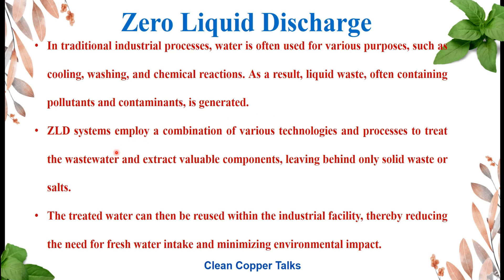A ZLD system employs a combination of various technologies and processes to treat wastewater and extract valuable components, leaving behind only solid and salt materials. Using thermal treatment or membrane-based techniques such as reverse osmosis, all water is extracted from the wastewater and all waste components are taken out as solid or semi-solid form. The treated water can then be reused within the industrial facility, reducing fresh water intake and minimizing environmental impact.